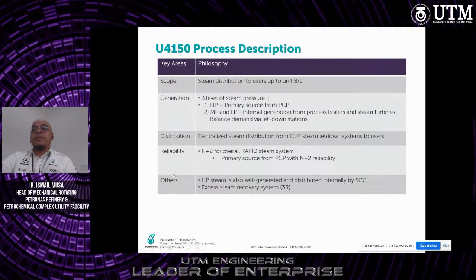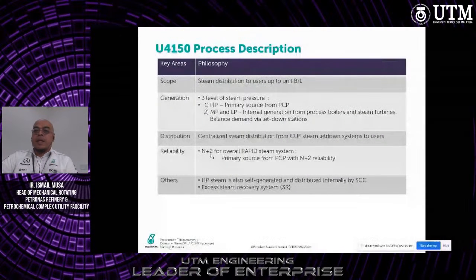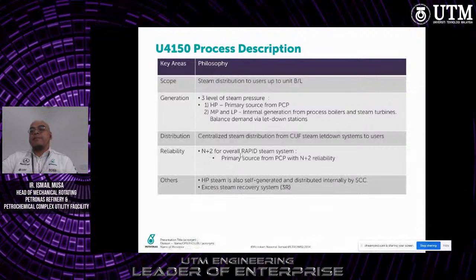For reliability, most of the design is based on N+2. N+2 means N is the number of equipment running plus 2 standby at all times for the overall steam system. The primary source from PCP has N+2 reliability. This is to ensure the plant is reliable at all times, able to supply the power and also the steam. This is the heart of the plant. If we have a shortage of power and steam, the plant won't provide the intended production, which is 300,000 barrels per day.